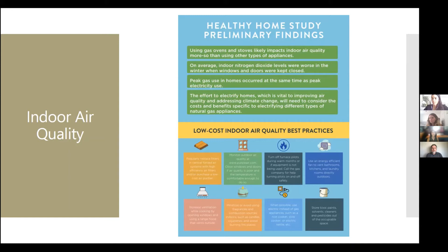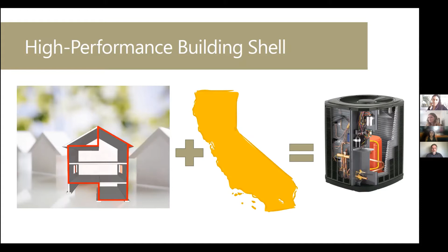Another thing about heat pumps and heating and cooling systems overall is that the topic of high performance buildings is at its peak, and having a high performance building shell reduces the heating and cooling system size you need. Where we used to size mechanical systems at a rule of thumb of about 1 ton per 400 square feet, we're not looking at that anymore, because a high performance building envelope reduces the sizing you actually need for heating and cooling.